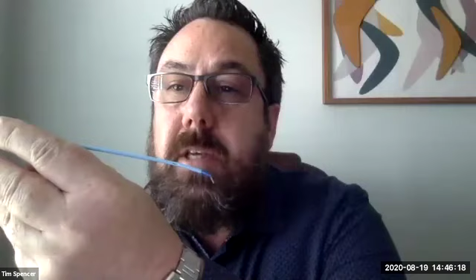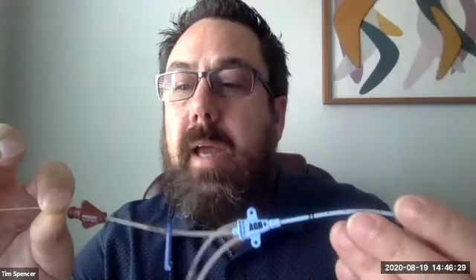Now, in this particular case, I'm just going to feed my wire into my catheter. If I can get it in, hang on a tick, sorry. So when we insert a catheter normally, we want to have a good amount of real estate in the vessel so that we can advance our dilator and our catheter. What I really want to do is, rather than confuse everybody about going backwards and forwards, bring the J-tip into the end of the catheter just so that the wire is exposed just at the end. And then we measure to the back of the hub. Now this is where we're going to put our alligator clip.